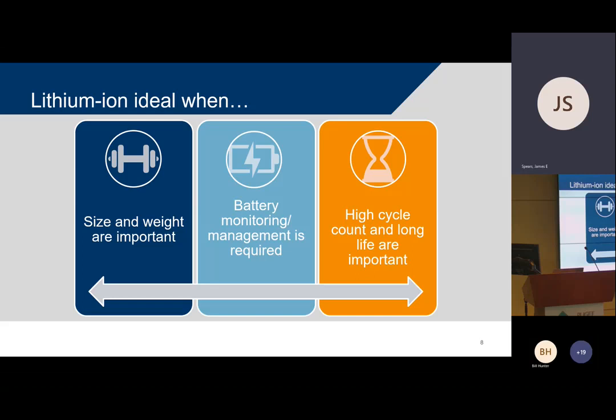But if that alarm isn't mitigated within a certain period of time, the battery management system will simply disconnect that string, whether the user wants it to or not. If there's a thermal issue that hasn't cooled off a few hours later, that battery is going to be out of the picture. That's different from traditional UPS batteries, where we just hope the battery we haven't maintained in years gives us a couple minutes in the next outage. If the lithium batteries aren't happy, Elvis leaves the building - we want everyone aware of that.